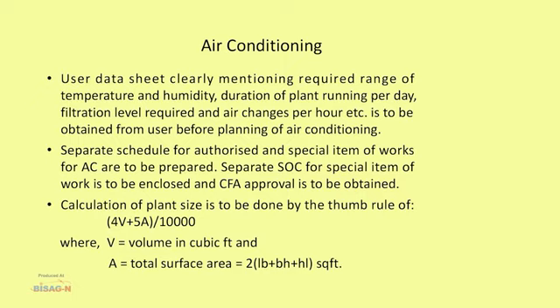Now talking about air conditioning. The user data sheet, clearly mentioning the required range of temperature and humidity, duration of plant running per day, filtration level required, and air changes per hour, etc., is to be obtained from the user before planning of air conditioning. Separate schedules for authorized and special items of works for AC are to be prepared.